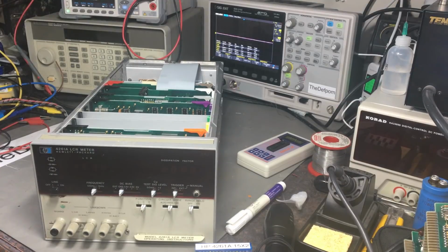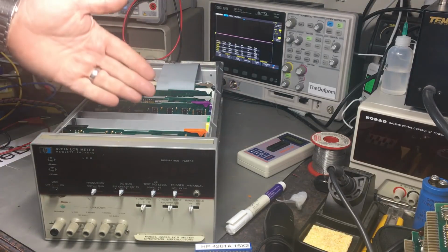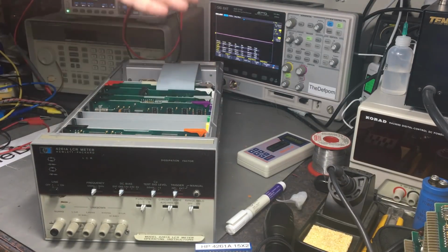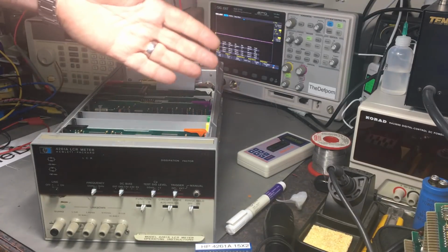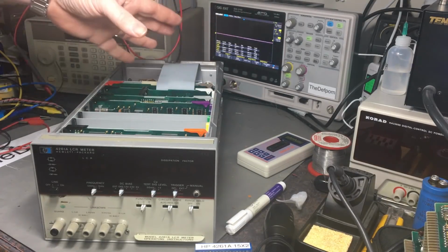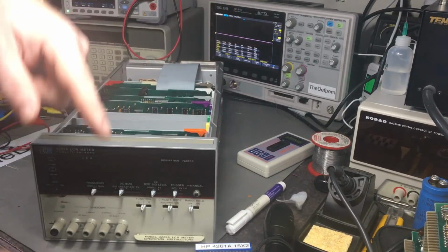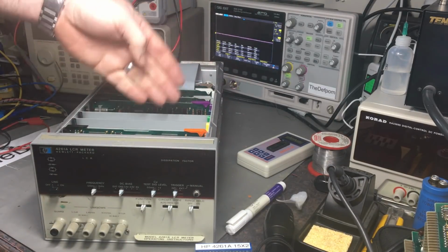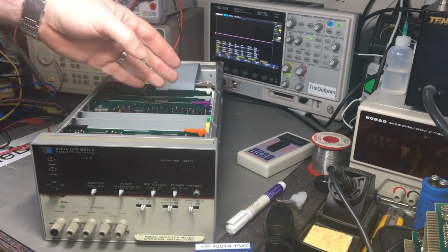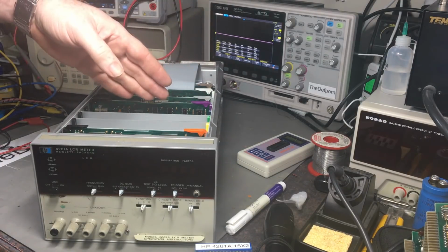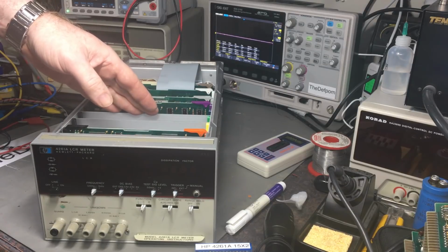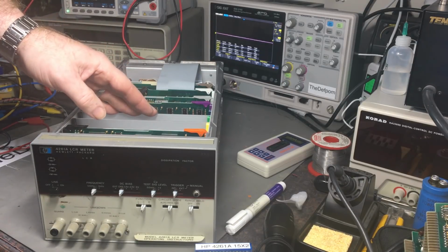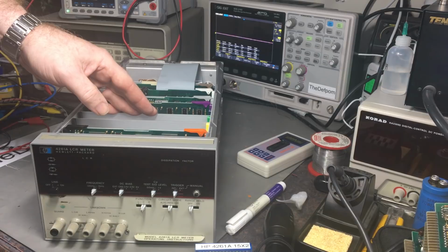So I've kind of gone back to where I started from one of my earlier tests. Now this is doing test 2 again, but it failed test 2, so now I go back to doing test 1. I removed the A4, 5 and 6 cards, and what I have to do is test for correct levels on the A3, A7 and A8 cards.